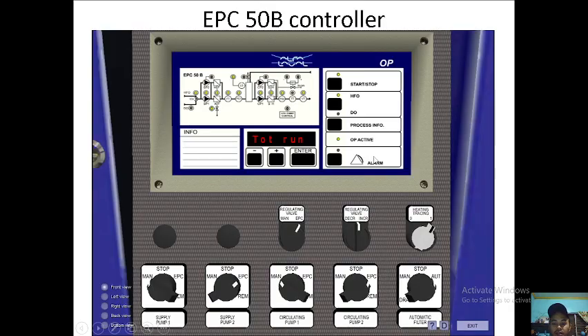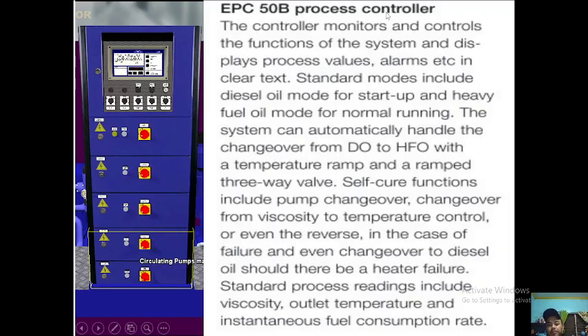So this is the EPC50B controller. Okay. So the EPC50B process controller monitors and controls the functions of the system and displays process values in here, so alarms, etc., and the clear text. Standard modes include diesel oil mode for startup and heavy fuel oil mode for normal running. The system can automatically handle the changeover from DO to HFO with a temperature ramp and a ramp three-way valve. Self-cure functions include pump changeover from viscosity to temperature control, or even the reverse, in the case of failure, and even changeover to diesel oil should there be a heater failure. Standard process readings include viscosity, outlet temperature, and instantaneous fuel consumption rate.